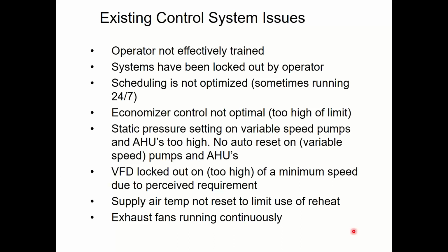They typically are set to provide way more pressure than is needed, because that's a safe answer, kind of like the scheduling: if I run it 24/7, the tenants aren't going to complain, right? If I put a schedule in there, maybe I was wrong and guessed that the time's wrong. Same thing happens with the static pressure on the variable speed fans and pumps. They put it at a higher pressure than they need, because the higher pressure means they're going to guarantee everybody gets enough airflow, but it could be wasteful compared to what the energy savings could have been.